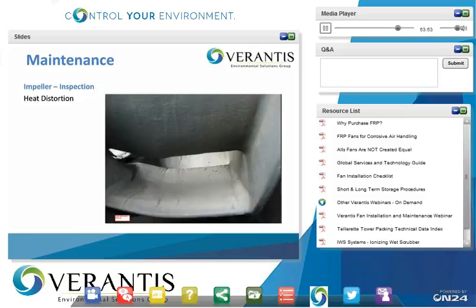Maintenance. Impeller inspection. Again, an access door is very critical for this portion of it. What we're showing here is a fan impeller that was subjected to high heat conditions, which were higher than the allowable for the resin that the impeller was made from. You can see the bowing and bending of the blades, where the blades are starting to warp and crack in the center. And also they would start tearing apart at the front ring joint and the back plate joint.